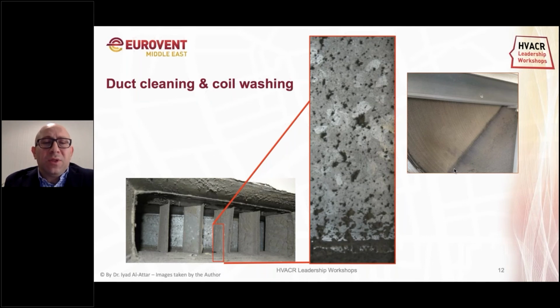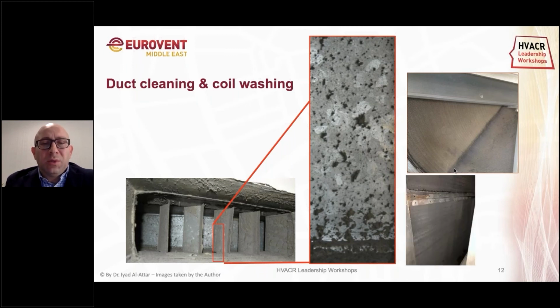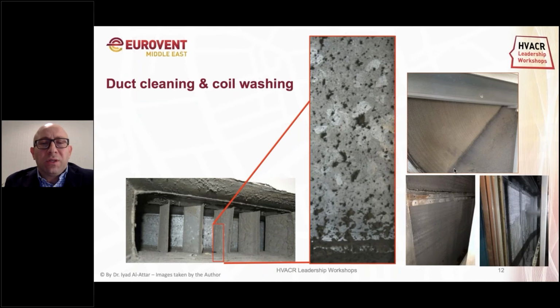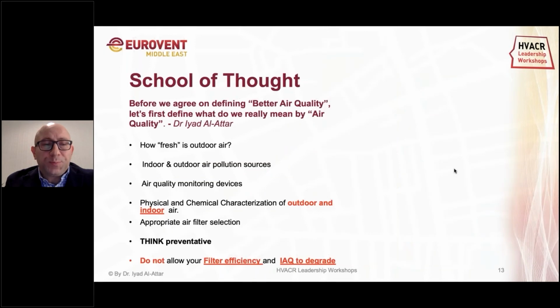As you can see now, the duct is full of dust, which is supposed to be caught as a preventive measure by the filter, and the coil is now participating in the filtration action, which is really not acceptable. Eventually, you have to wash the coil, disinfect it, and remove the dust so it can perform the expected heat transfer and the heat transfer mechanism is restored.